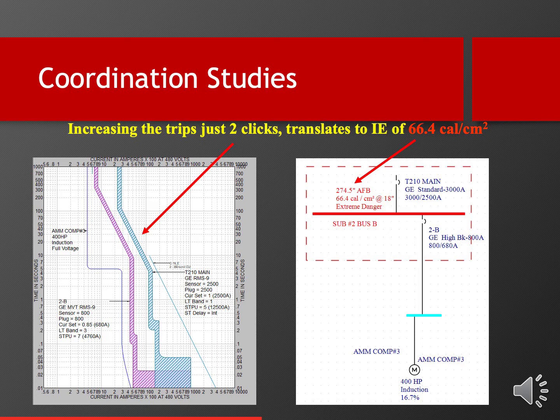Now, I will also be careful to tell you that if you don't maintain your circuit breakers, you'll get the same result. That breaker could be delayed in its tripping, retarded in its tripping time, and you could have way more incident energy that's actually there than what you see on the label. So that's an important point, and I can't overstress the importance of it because this happens on the job sometimes on purpose, where people have nuisance trips, and sometimes inadvertently because of maintenance deficits. Let's go to the next slide.